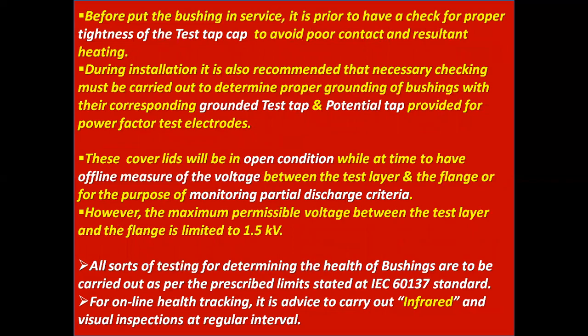Before putting the bushing in service, it is necessary to check for proper tightness of the test tap cap to avoid poor contact and resultant heating. During installation, it is also recommended that necessary checking be carried out to determine proper grounding of bushings with their corresponding grounded test tap and potential tap provided for power factor test electrodes.